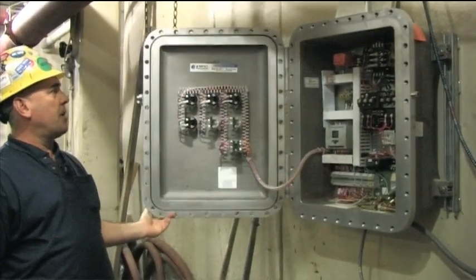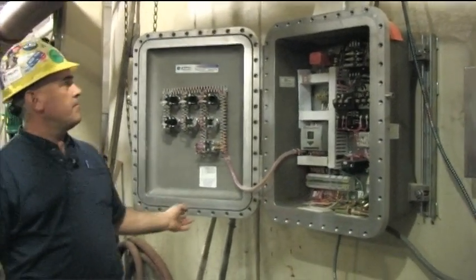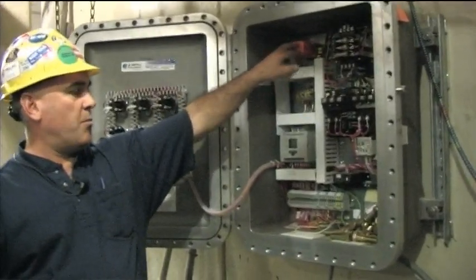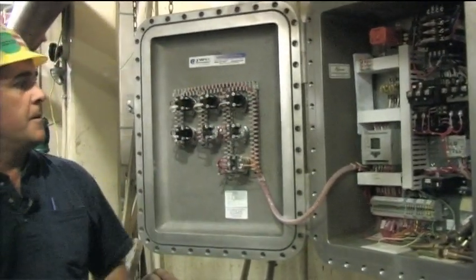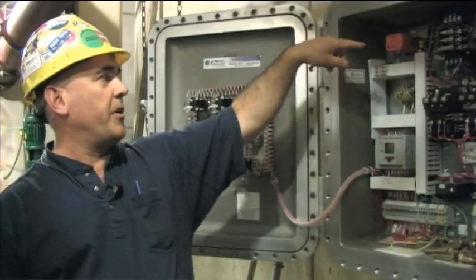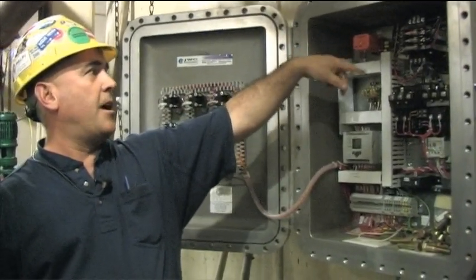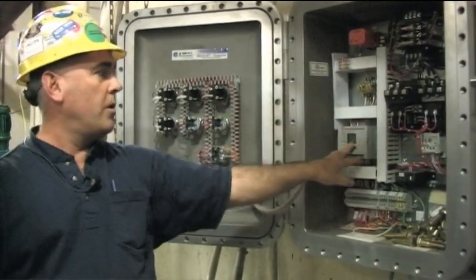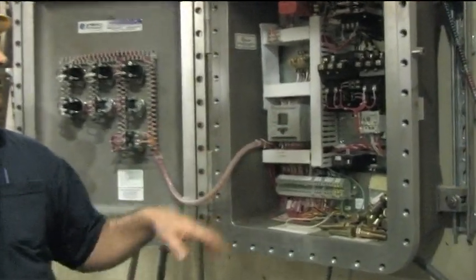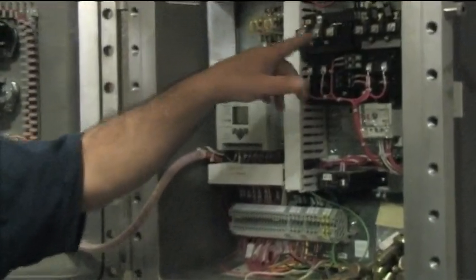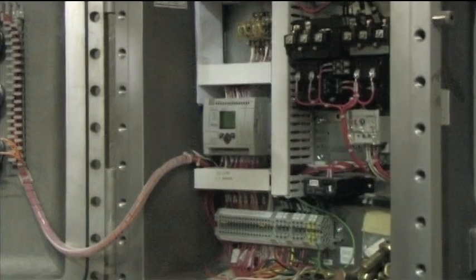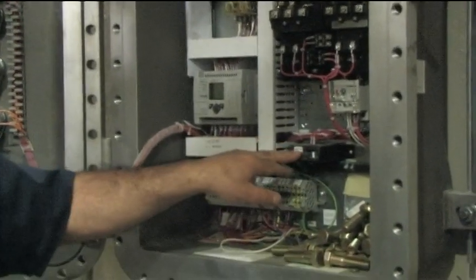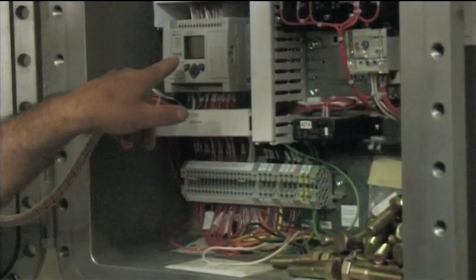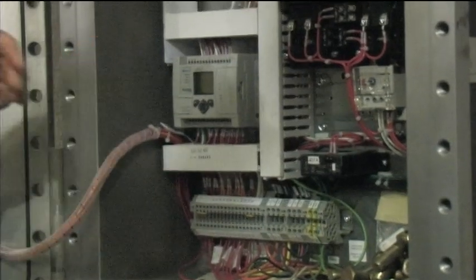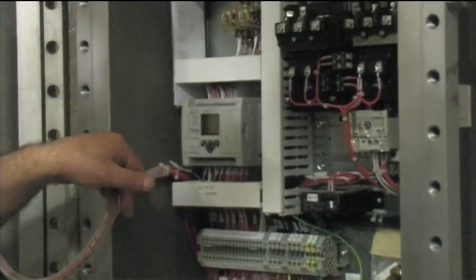Inside the panel itself, again, this is just your phase monitor monitoring the incoming current. Line voltage coming in to step-down transformer for the control circuitry here. You have a forward and reversing contactor, the current transformer, and the PLC, which is the brains of the unit.